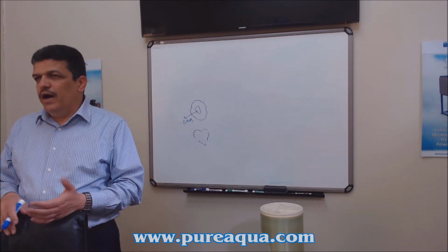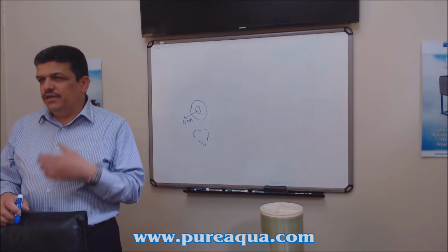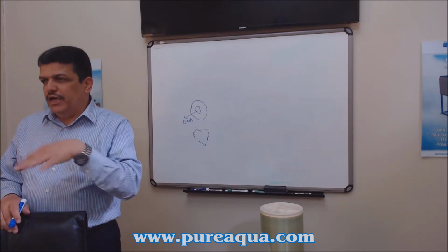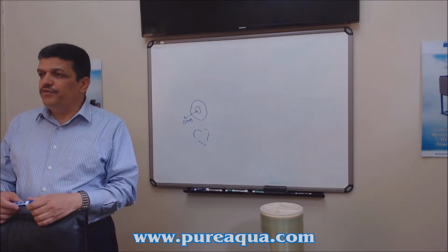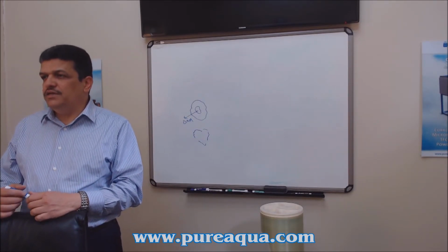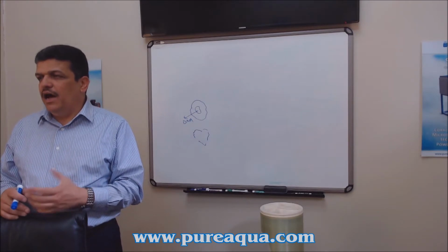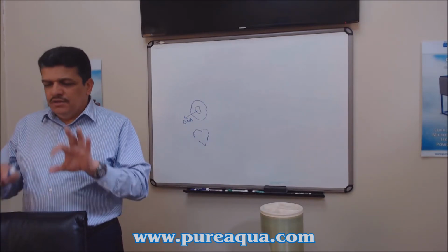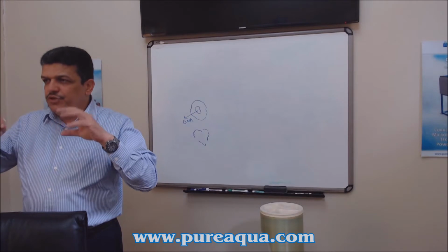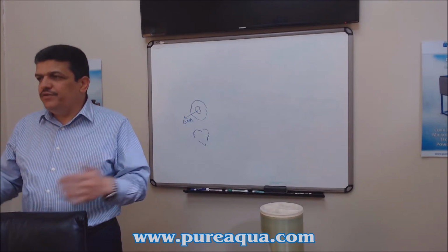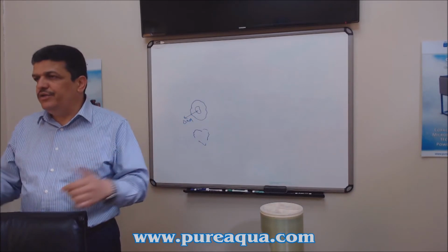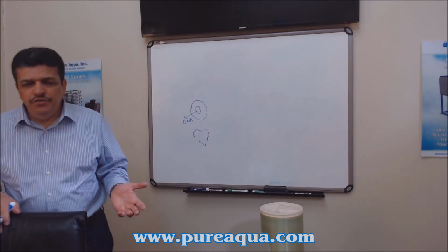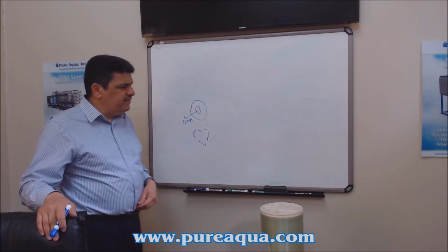Because the light is going to penetrate the water and get to that virus and bacteria. And the second thing, for future maintenance: can you imagine that the water has high NTU or high turbidity? The quartz sleeve inside is going to become turbid slowly. Then the UV intensity is not going to penetrate through the water, so it's going to be useless.